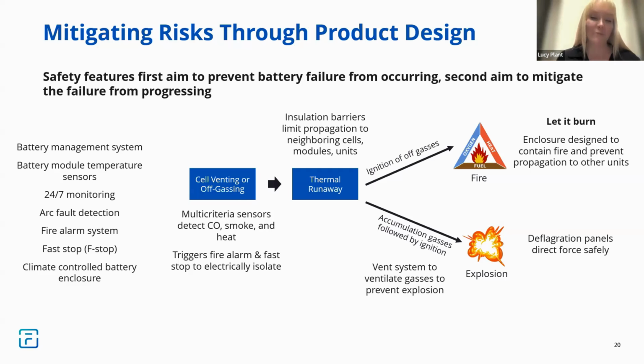Within LFP cells, what we do see is that, although off-gassing can occur, it is very unlikely that it would move to a full thermal runaway event, although it can, and that is what we have to prepare for. So what you want to do is monitor that remotely. Fluence's new systems, the GridStack Pro and our SmartStack systems, our latest product offerings, have integrated gas sampling manifolds at the top, middle, and bottom of each container. That allows first responders to have eyes inside that container to monitor those gases as they build up, without the need to open the door and risk any sort of explosion.